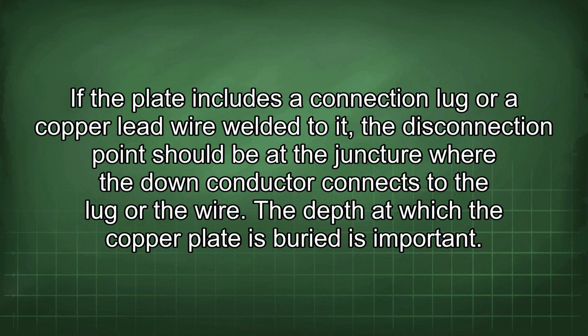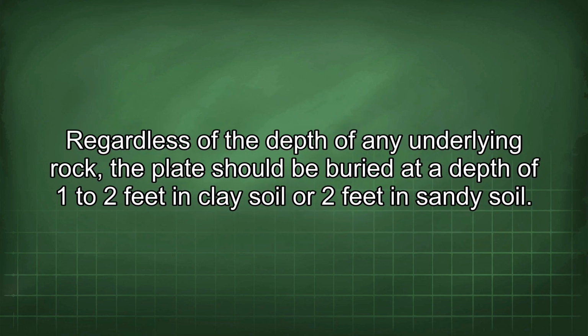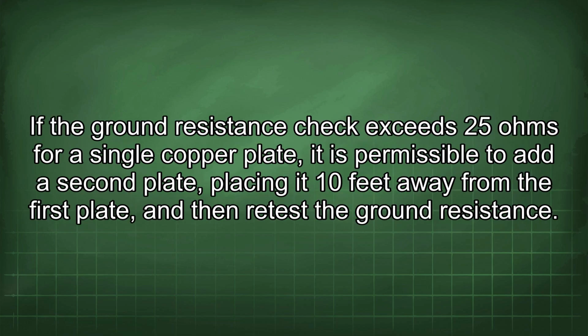The depth at which the copper plate is buried is important. Regardless of the depth of any underlying rock, a plate should be buried at a depth of 1 to 2 feet in clay soil or 2 feet in sandy soil. If the ground resistance check exceeds 25 ohms for a single copper plate, it is permissible to add a second plate, placing it 10 feet away from the first plate, and then retest the ground resistance.